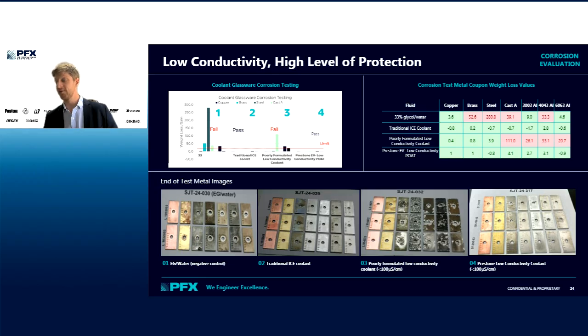And we can see just from the visual of the poorly formulated low conductivity end of test specimen that these specimen have been terribly eaten away and corroded by the fluid in there. And so this fluid is actually a fluid that was commercialized as a low conductivity EV fluid prior to the GB specification being released. This fluid was later recalled due to corrosion issues within the system. Now, what does a good fluid look like at low conductivity? You'll see the results are much, much closer to that traditional ICE coolant.